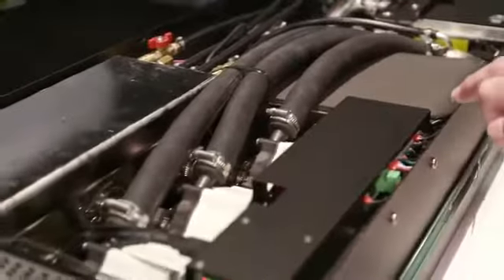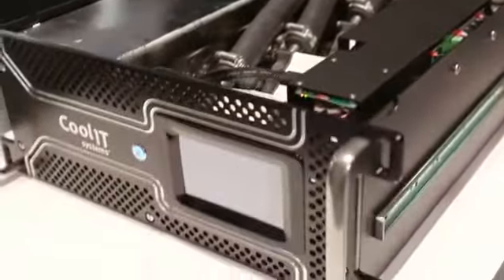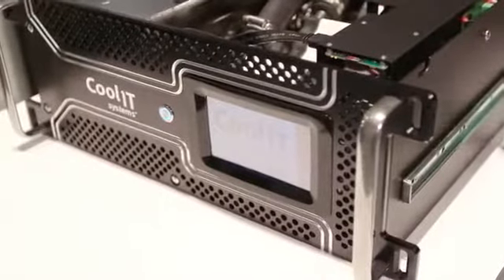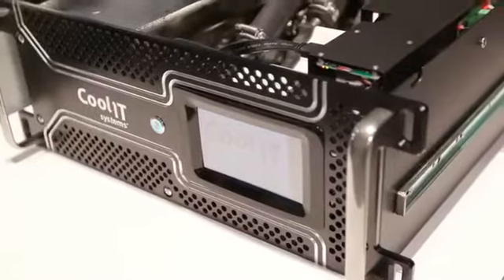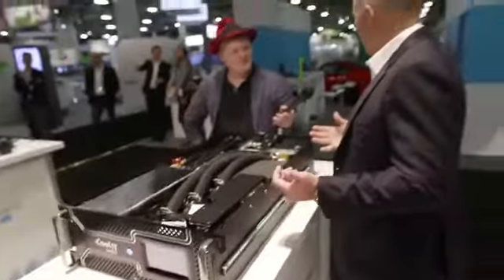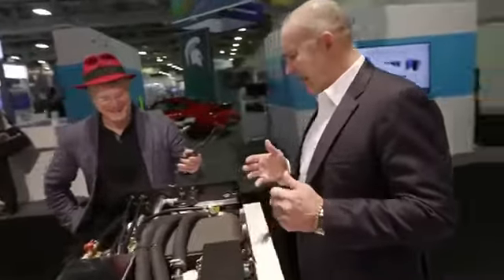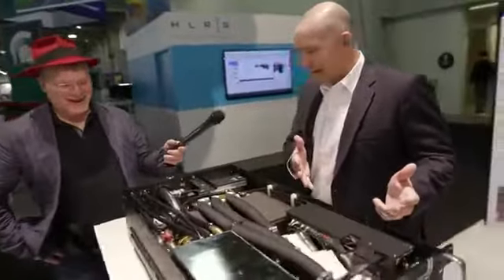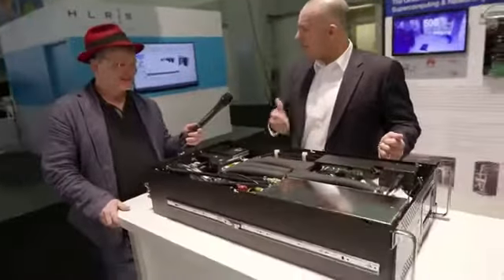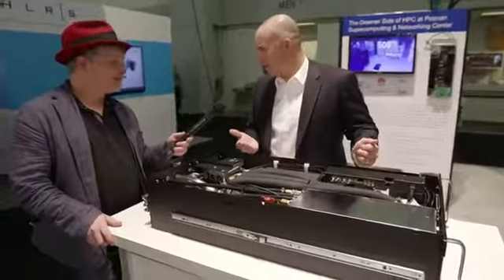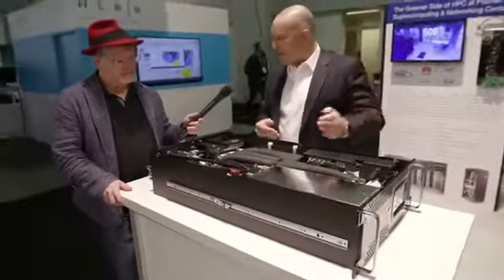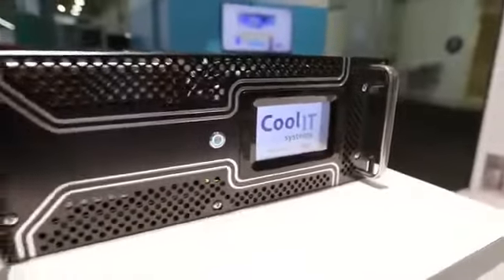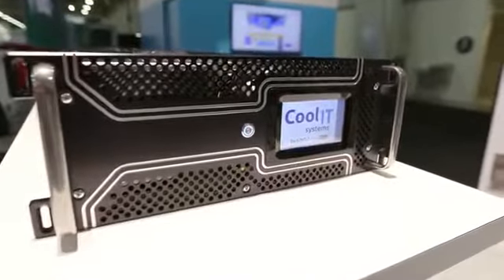But what we do, in fact, once a day, is we give each one a day off in succession. So it has an even wear life. And also, if you have your backup pump and you have one fail, you don't want to find out then that your backup pump doesn't work. So it goes through that rotation. It is customizable if you wanted to have it at a different cadence.